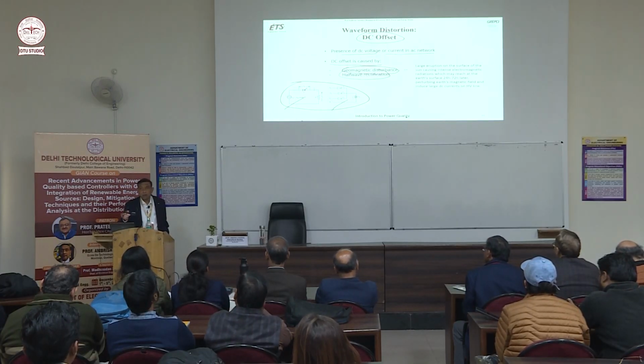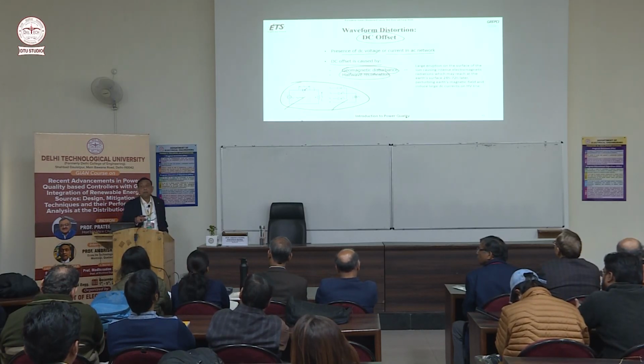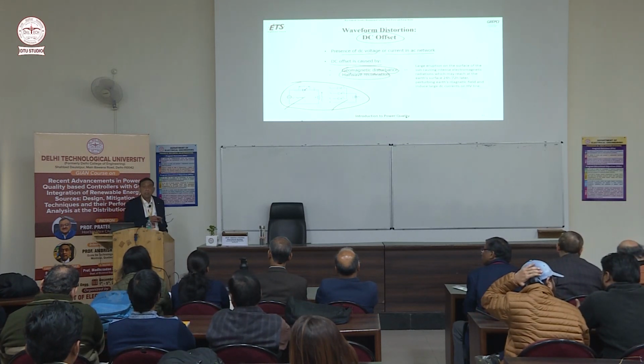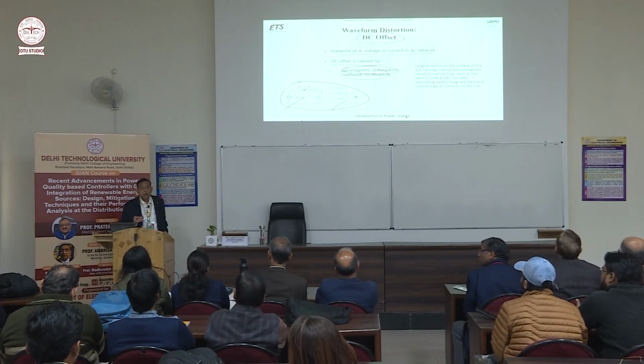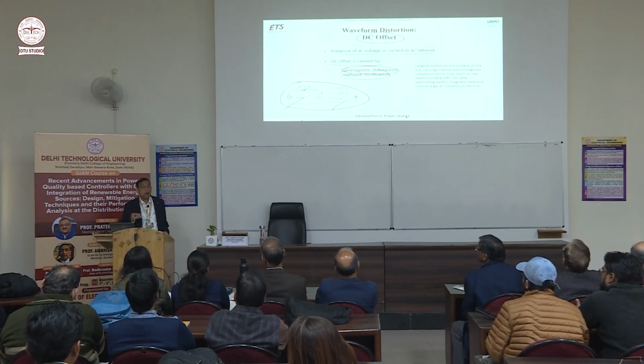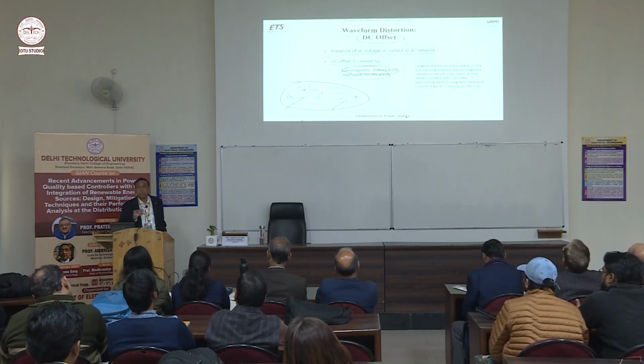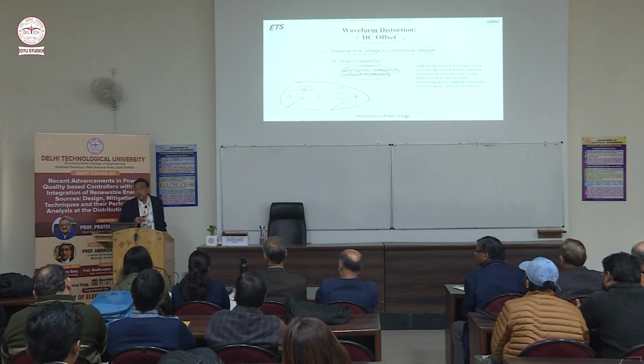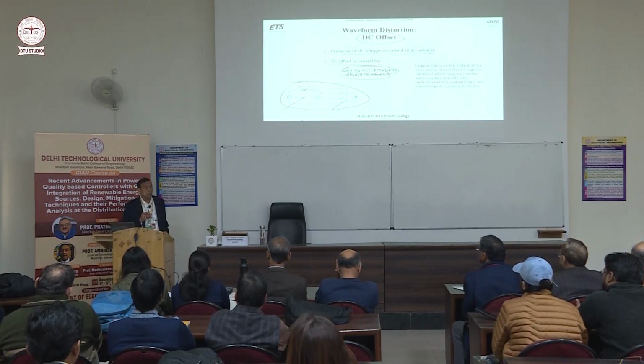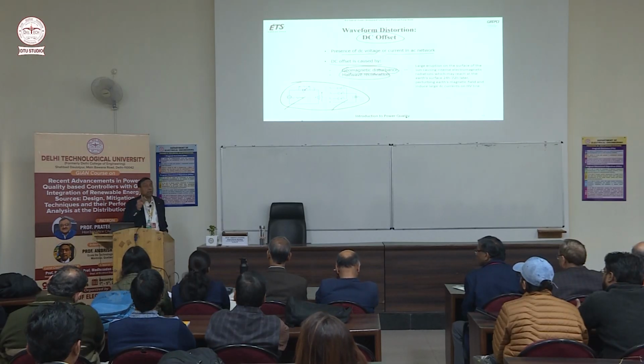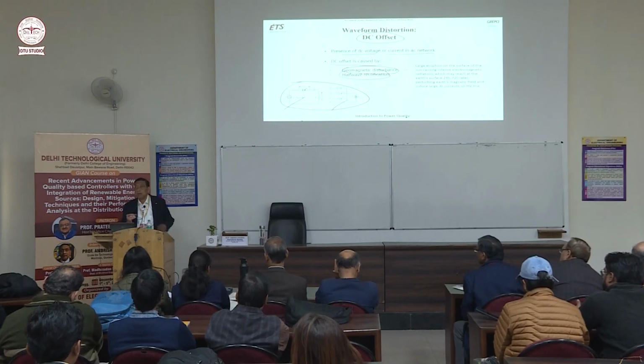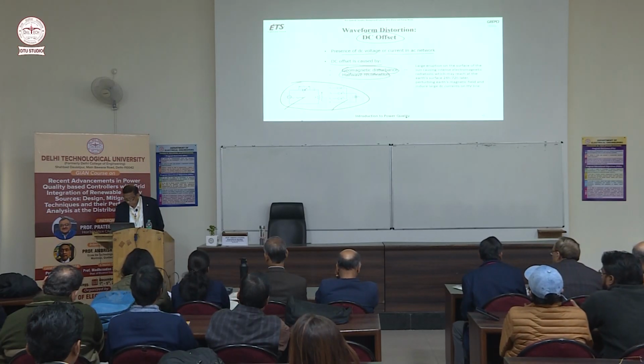And even in Quebec, in my home province, in 1990 it happened. There was a big eruption of electromagnetic waves from the surface of the sun, which reaches the earth between 24 hours to 72 hours. And that induces current on the earth's surface and on high voltage transmission lines. So it saturates the transformers and other equipment because this is a DC current which is induced. This is what happened around 30 to 35 years ago in Quebec. All the high power networks were down for many days. They did not know what happened, but then they analyzed it and came to know this was caused by those eruptions at the surface of the sun.